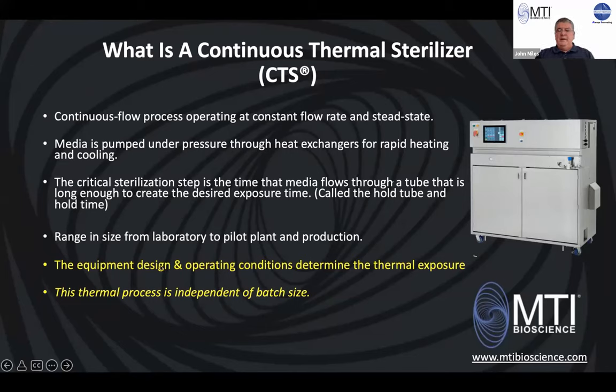The equipment design itself and the settings we use, the operating conditions, determine the thermal exposure. And that's really the nice part, because the thermal exposure is what determines the quality of the media. In this kind of equipment, it's independent of batch size.